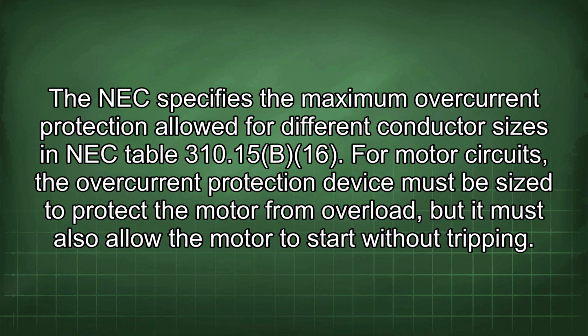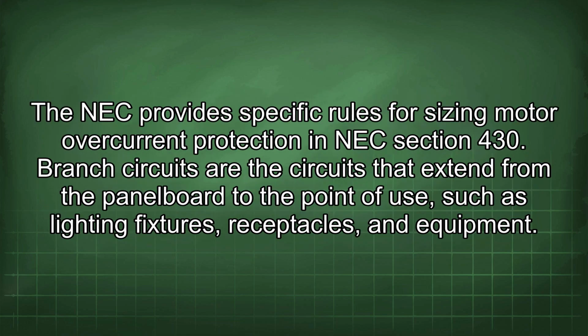For motor circuits, the overcurrent protection device must be sized to protect the motor from overload, but it must also allow the motor to start without tripping. The NEC provides specific rules for sizing motor overcurrent protection in NEC Section 430.